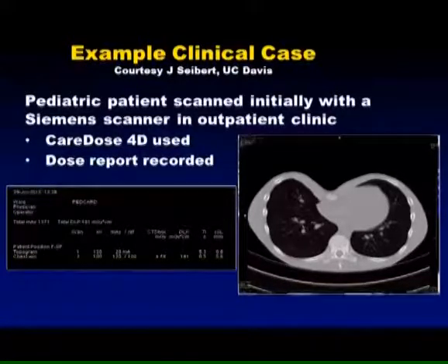But I will say this. If you make the measurement at the thinnest point of the patient, what will you do? Will you overestimate or underestimate the dose? You'll overestimate the dose. If you make your estimate of size at the thickest point of the patient, you'll underestimate the dose. I would advocate that you pick a thicker point and a thinner point and do some kind of weighting to come up with one thickness that you're going to use to reduce the amount of error, because we only have one CTDIvol.